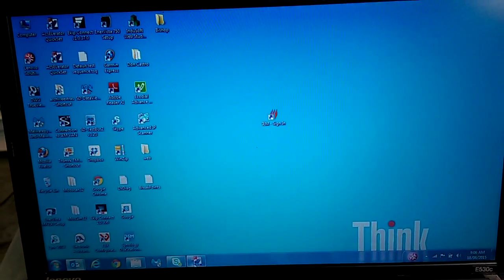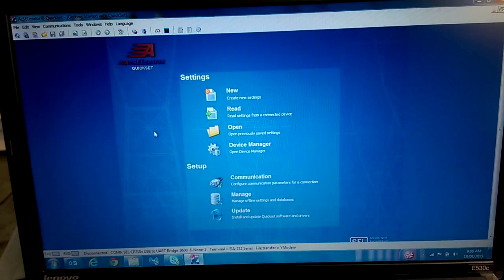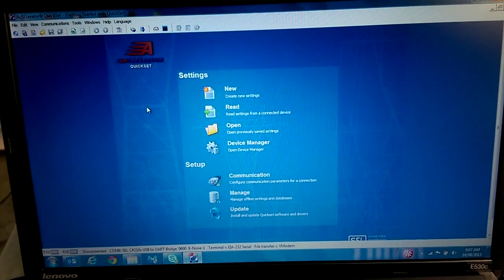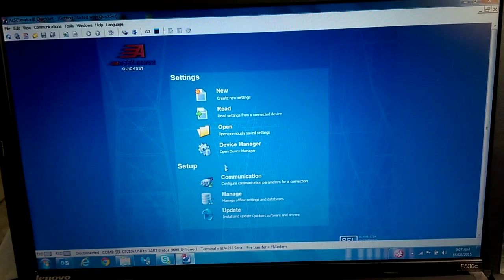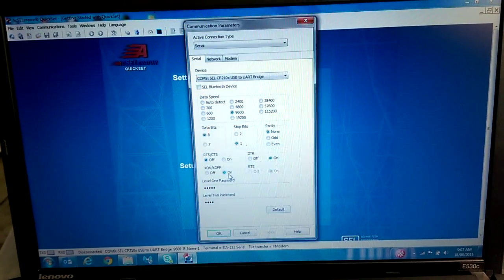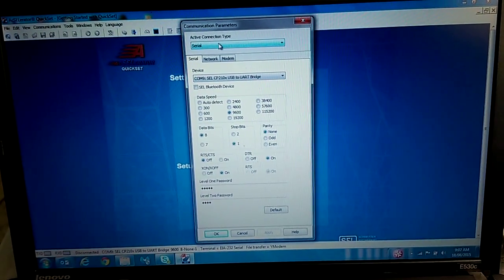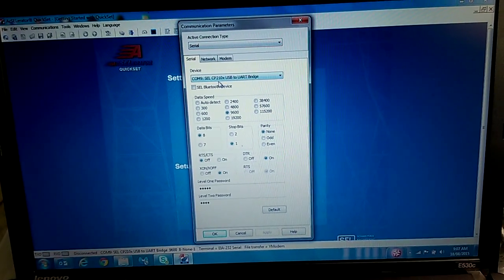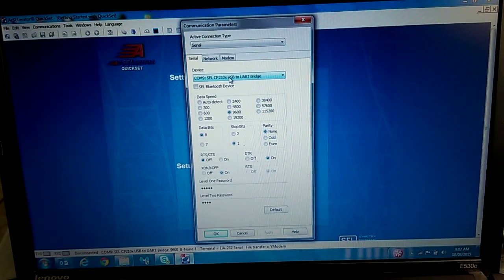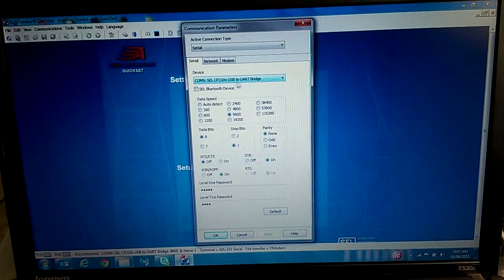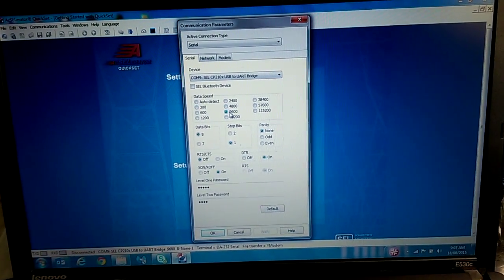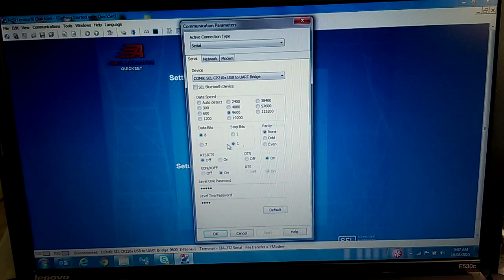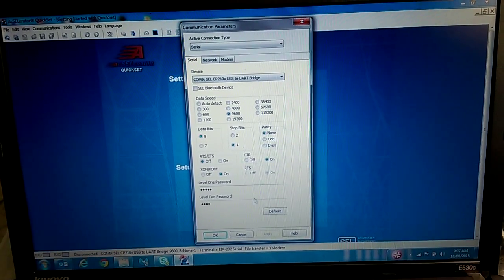Then we're going to open the SEL Accelerator Quick Set. We'll go down to Communication and make sure that our connection type is Serial. And you select the COM port that that serial to USB is. Your baud rate will be 9600. And just go through and make sure that all the settings are as shown.